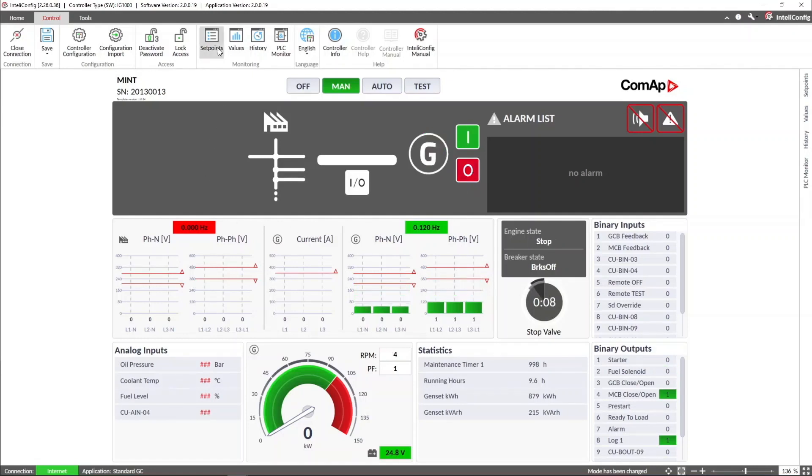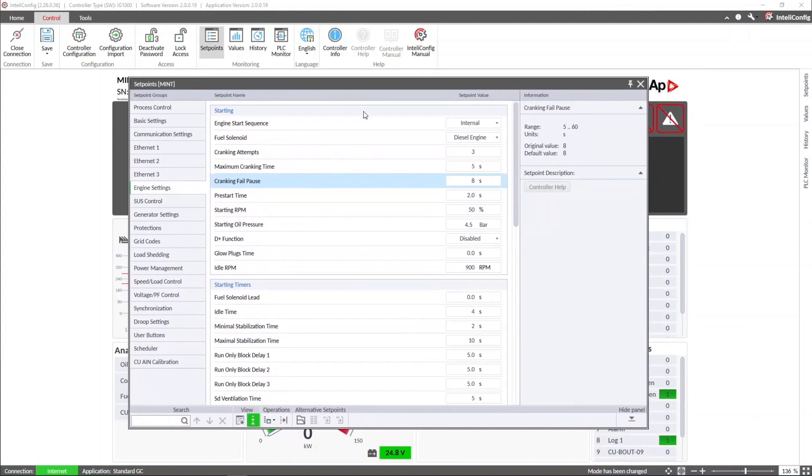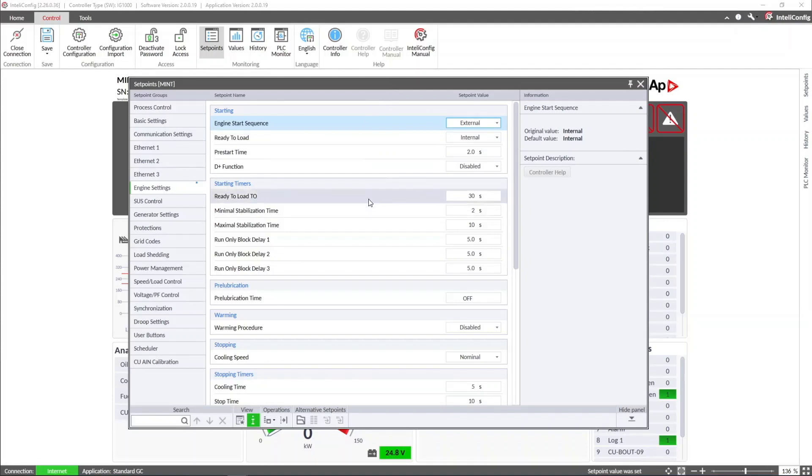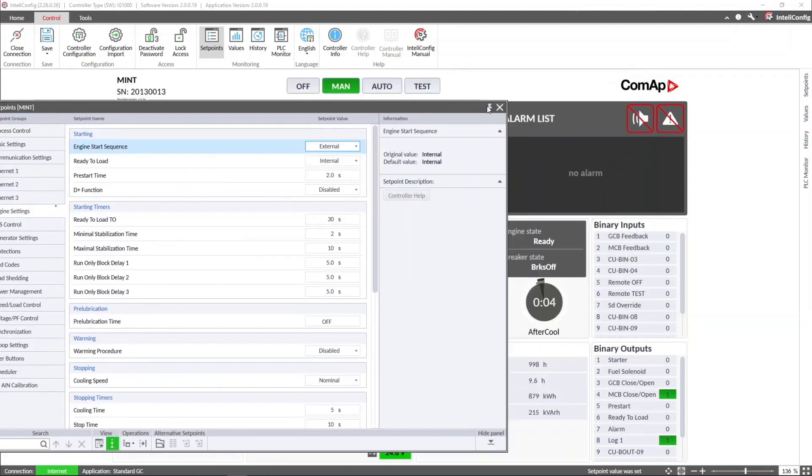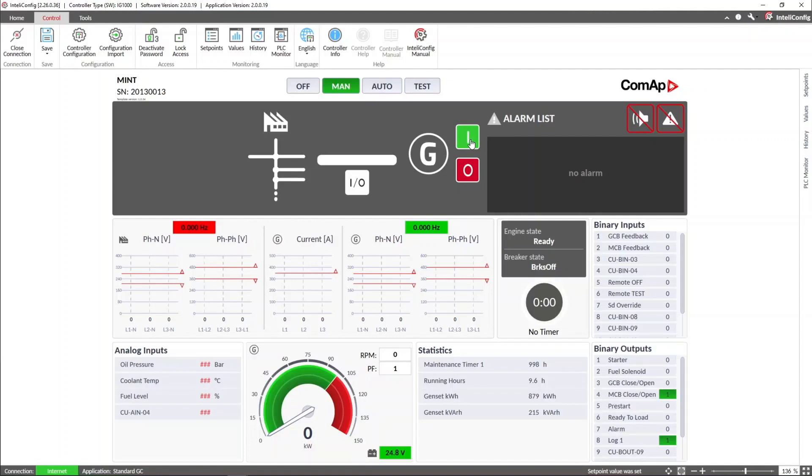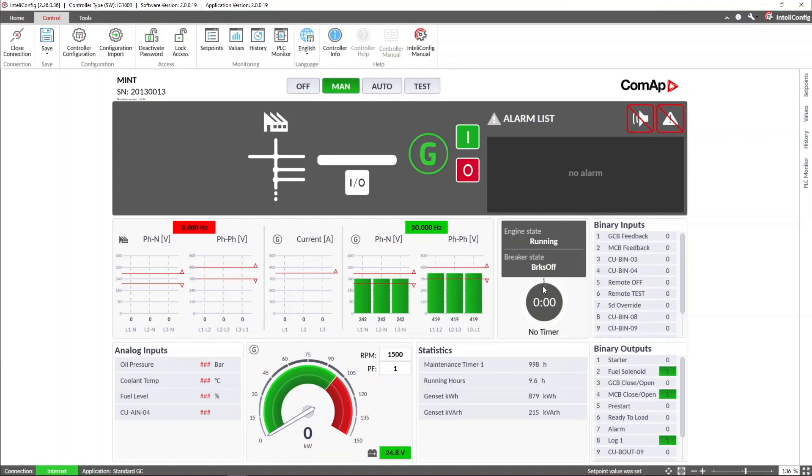If we change the engine start sequence to external, we must set, as I said before, the ready-to-load timeout. Then if we try to start the engine again, we can see how the controller just activates the fuel solenoid output after the pre-start time, and then starts counting down the ready-to-load timeout we set, and the minimal stabilization time once the voltage and frequency are within the limits.